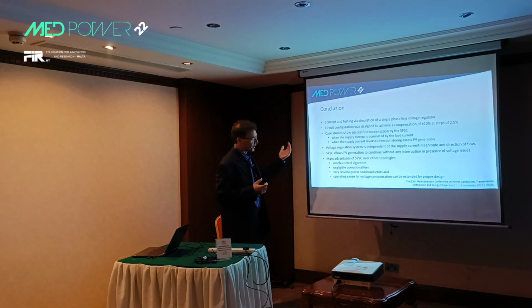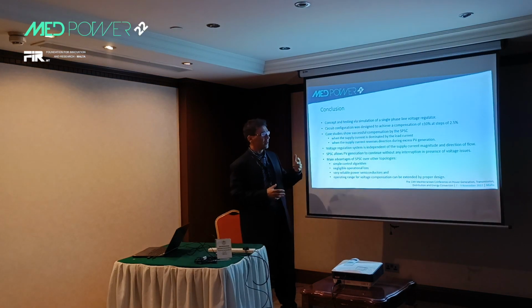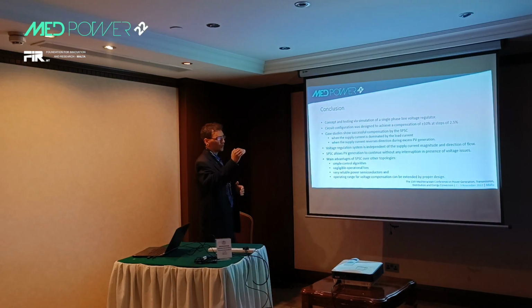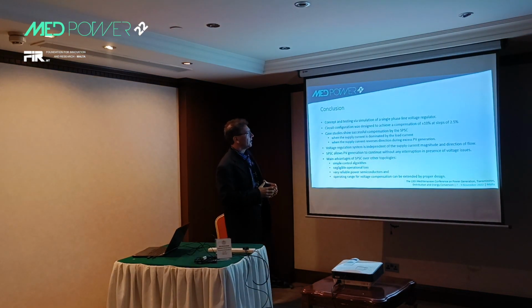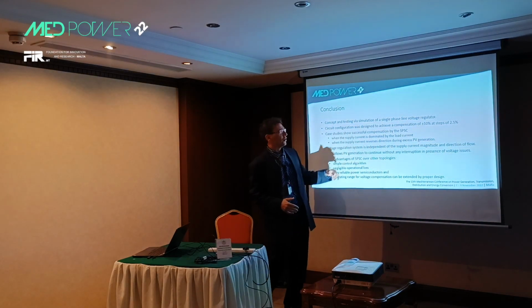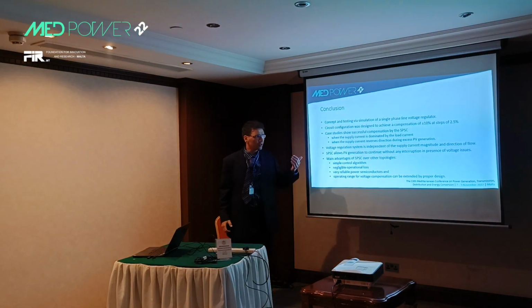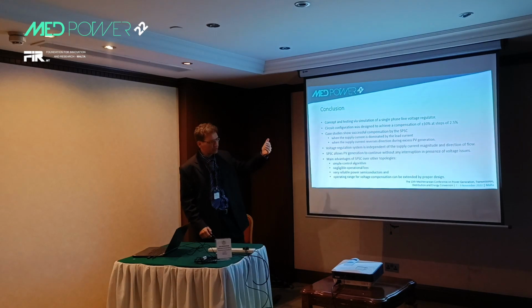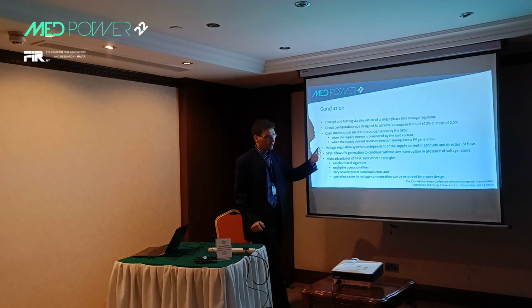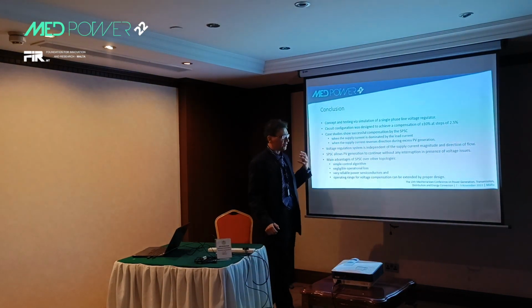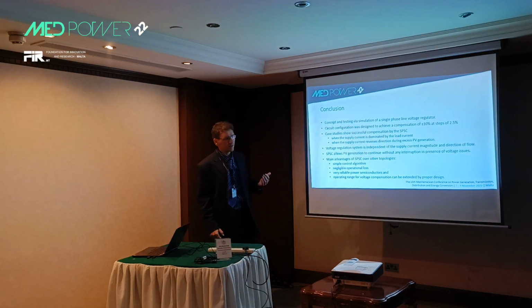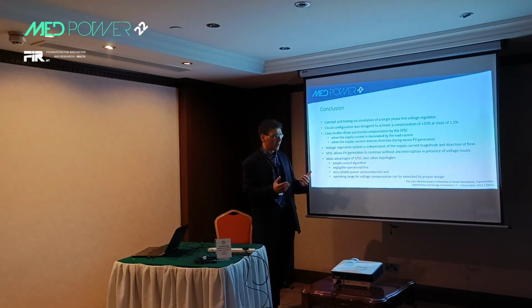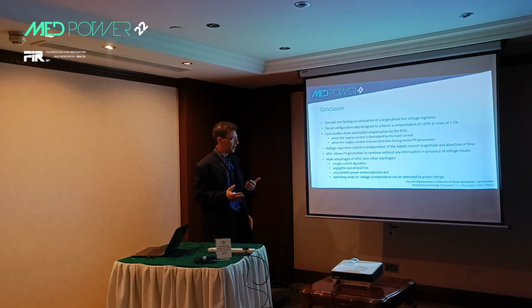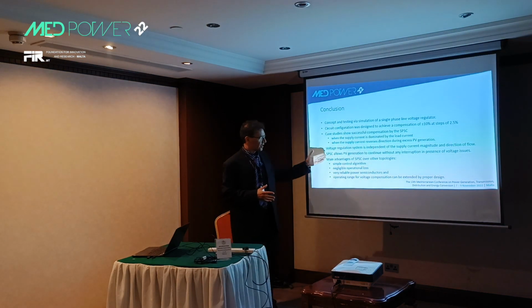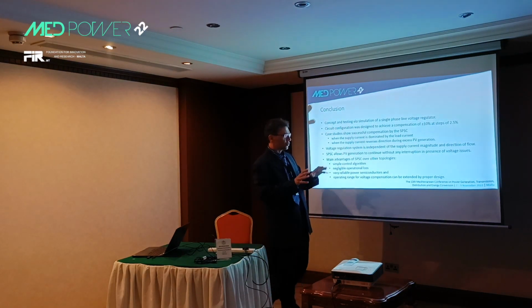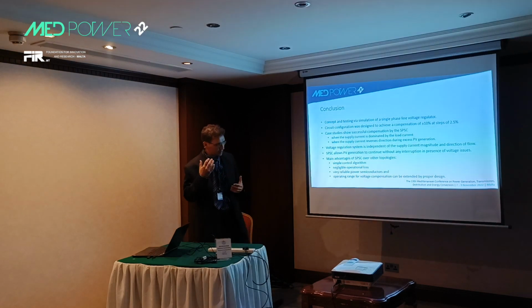The circuit is designed to give compensation of up to plus or minus 10% on the voltage, with steps of 2.5. We have seen that it works correctly both when we have load current, when we have a high load current, and also when we have an excess of PV generation. It is independent of the supply of the current and the direction of the flow of the current. As I said, it will allow your PV system to continue to work without there being problems on the voltage.